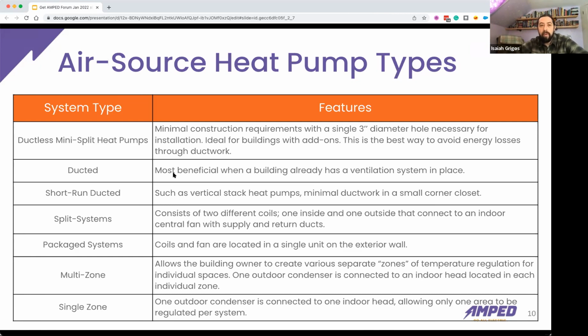We see a lot of these systems for a couple reasons. Basically, people like the aesthetics of a ducted system better, and they also deal with small rooms better. When you have a split system heat pump, you try not to oversize the equipment. And basically a ducted system allows you to adequately size for multiple rooms. So it reduces the risk of oversizing equipment. Short run ducted is a variation of that. And basically usually you have less than 10 feet of ductwork, and you can serve a couple different rooms just by cleverly placing your indoor unit.